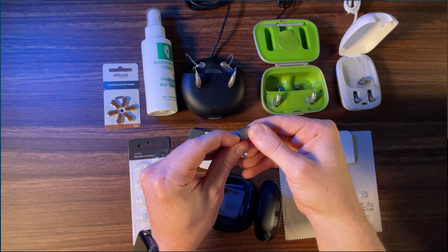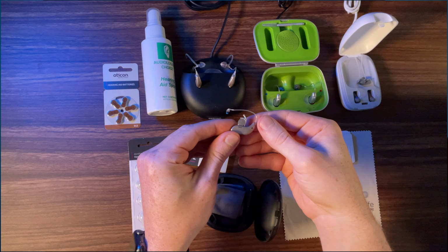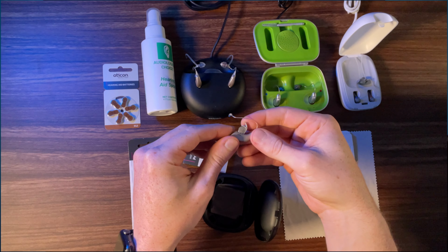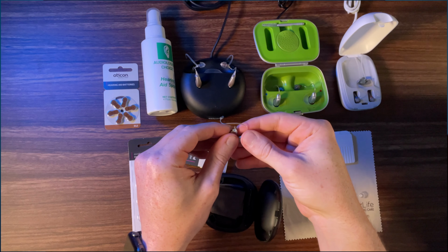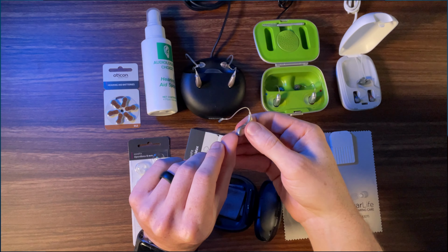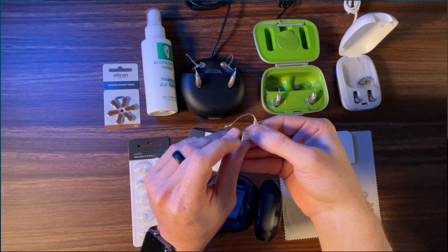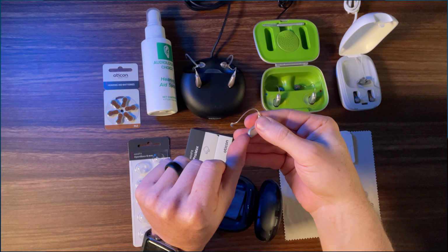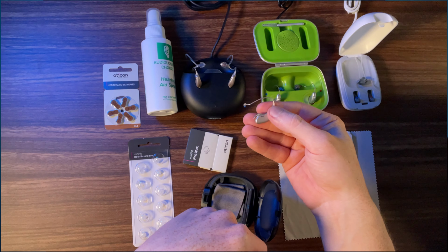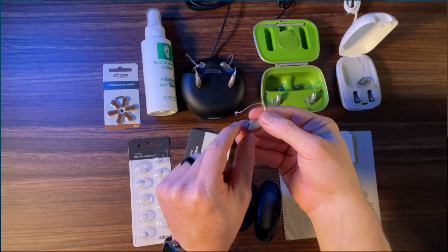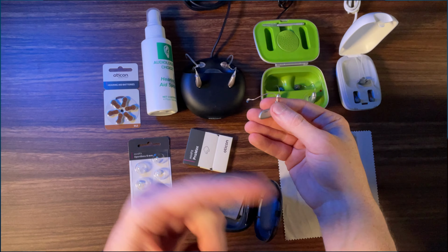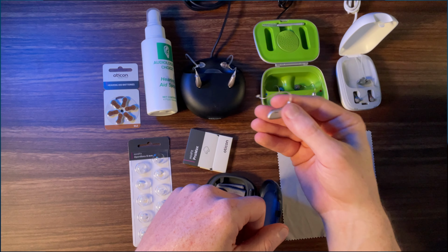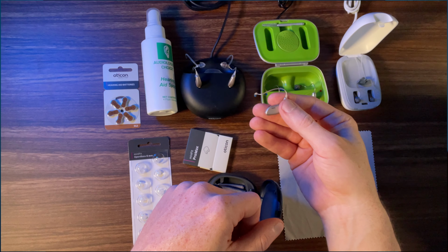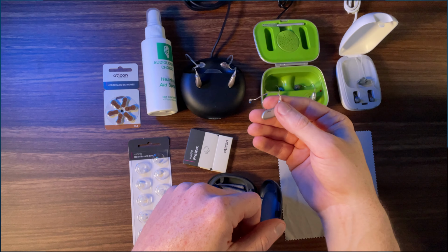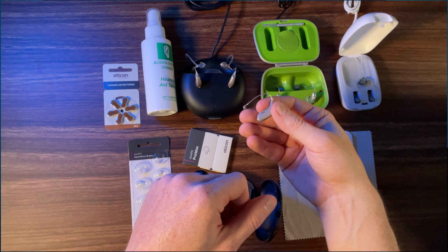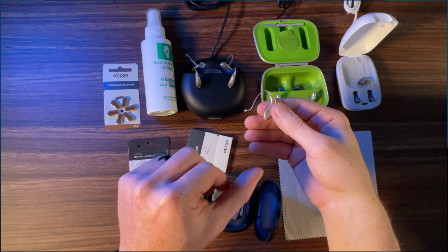Another style, which is also still out there and still fairly popular, is a disposable battery powered hearing aid. So you can see with this particular hearing aid, the battery door is on the bottom of the device. So with these, when you take them out at night, you just want to crack the battery door open. That's going to turn the device off, and then in the morning when you put it back on, you're going to shut the battery and that will boot it back up. Batteries on these devices can last anywhere from 3 to 10 days depending on the type of hearing aid, your hearing loss, the size of battery, and other factors.